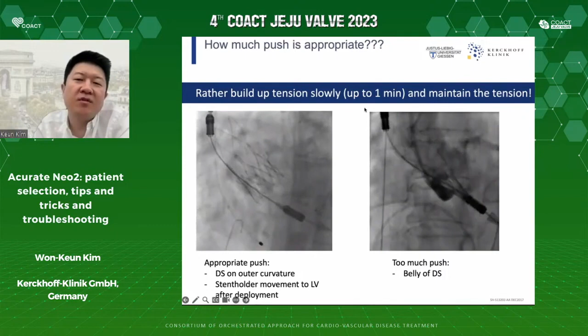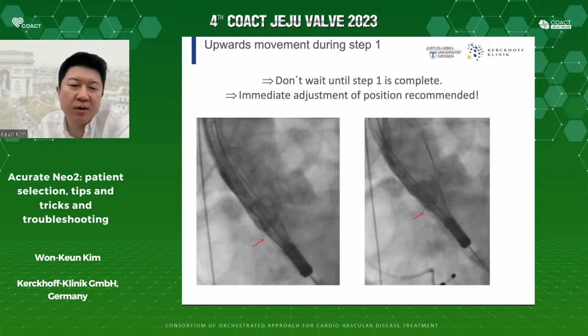And my personal opinion is, if you get too high, then you should really initially start to adjust the position. Don't wait until step 1 is complete. I think it's important to have immediate adjustment. You see this upward movement during step 1 quite frequently. And here's also a very nice example that we had recently. During step 1, we are still fine with the position. And you will note that during opening of the upper crown, the valve is moving higher and has ended up very high. This is too high.